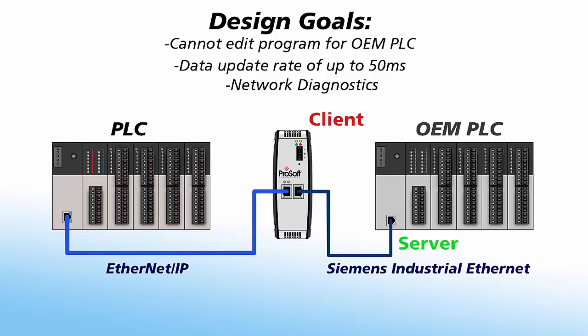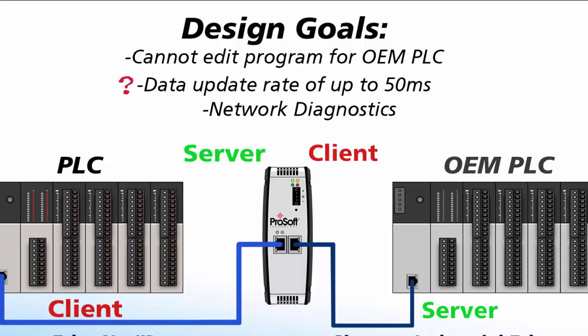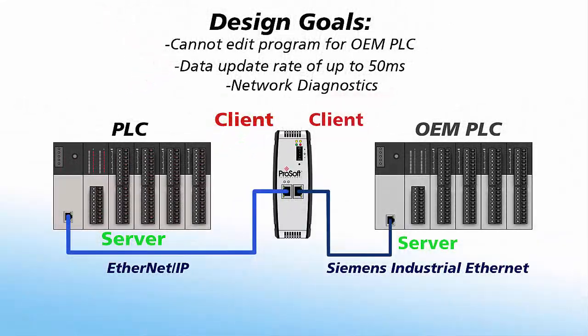When our gateway's port is configured as a client, it has a poll rate that sets your communication update interval and does not get sent at a lower priority like a PLC client message. This gives you fast, consistent communications. Like before, we could use message instructions in our PLC acting as a client to communicate to the gateway as a server, but our EtherNet/IP communication speeds will be dependent on the timing of the PLC's ladder code and any other EtherNet/IP communications that may be going on. Getting data transfers in under 50 milliseconds could be difficult. To avoid using message instructions, we could configure our gateway as a client on the EtherNet/IP side and the PLC as a server. This would eliminate the dependency on ladder logic timing and would also not require program changes.